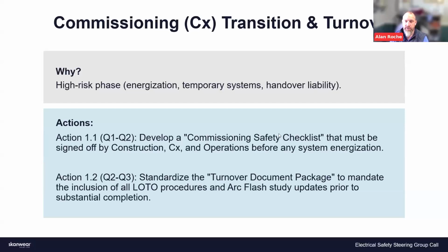That's a good, big question. As Dan alluded to, it's definitely different project to project, jurisdiction to jurisdiction. Some electrical contractors have a slightly different lockout tagout process, and as long as everyone understands and buys into that process at the initial project kickoff, it's fine. Trying to change it during the project can be cumbersome and difficult, but if it needs to change for safety's sake, change it. I've seen cases where we changed the rules of lockout tagout in the middle of a project and everyone got mad at each other.